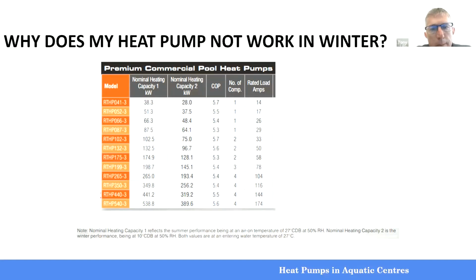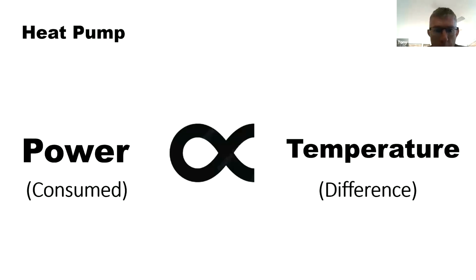Okay, so this is a data sheet from a heat pump manufacturer. And you'll notice that he's got 2 columns of capacity. Capacity 1 is the heating capacity at 27 degree ambient temperature, and capacity 2 is the heating capacity at 10 degree ambient temperature. So you can see from the difference in the 2 columns that there is definitely a difference in capacity between the 2 different ambient temperatures. And if we look at the bottom, the biggest capacity, it's rated as a 540 kilowatt heat pump. At about 4 degrees in Melbourne, that'd only give you about 300 kilowatts. So this is why your heat pump doesn't work in winter, it's just not really big enough.